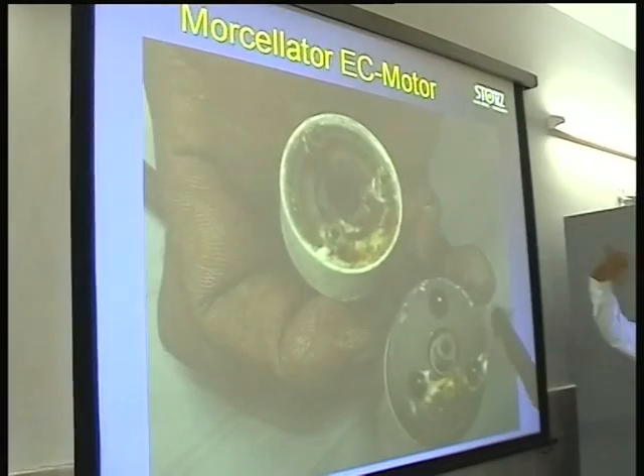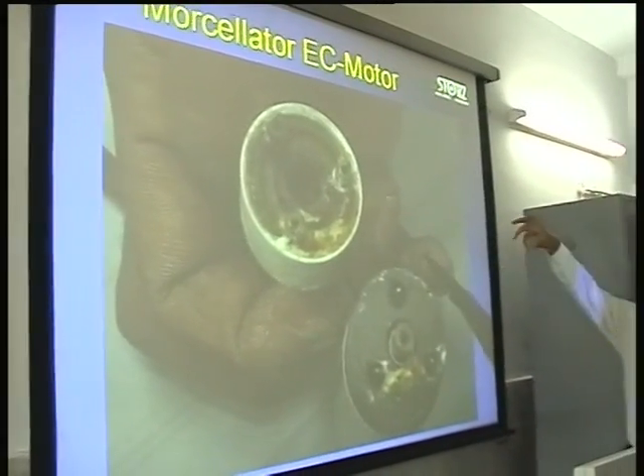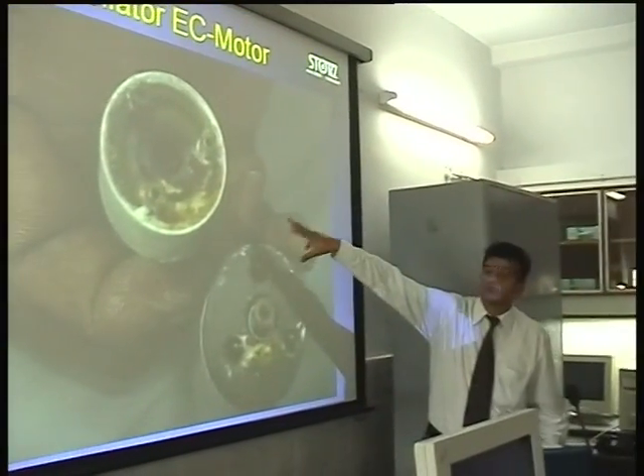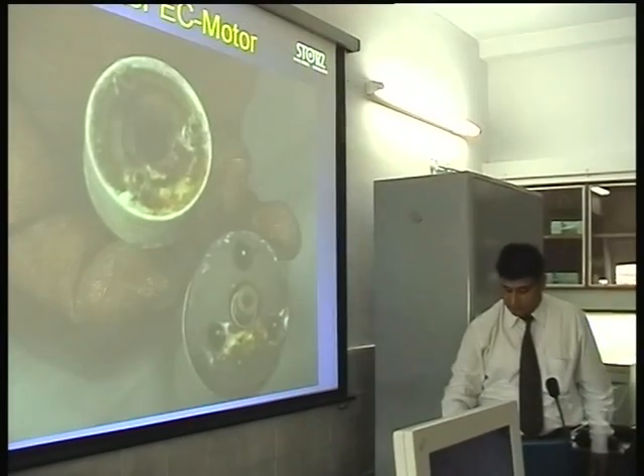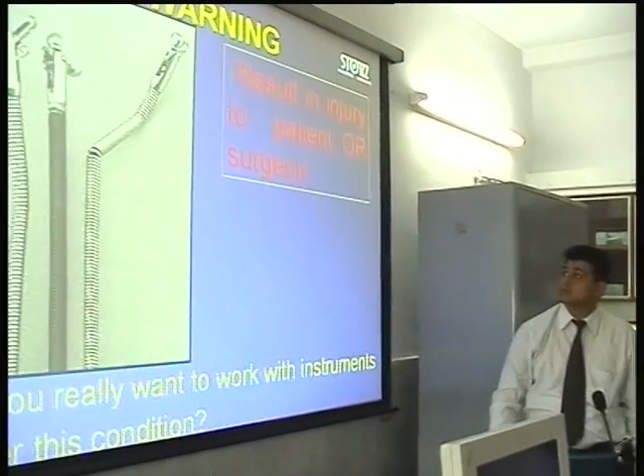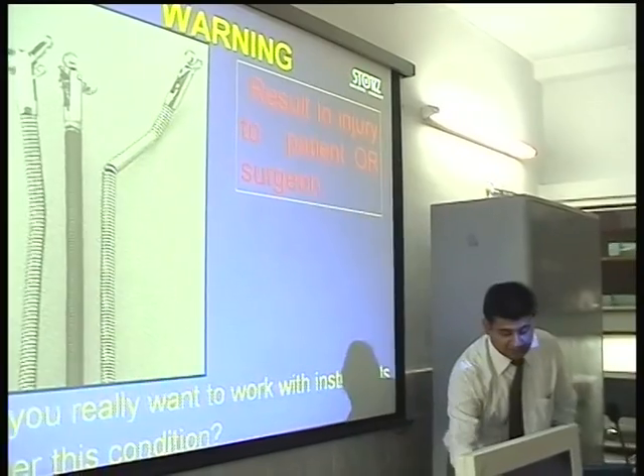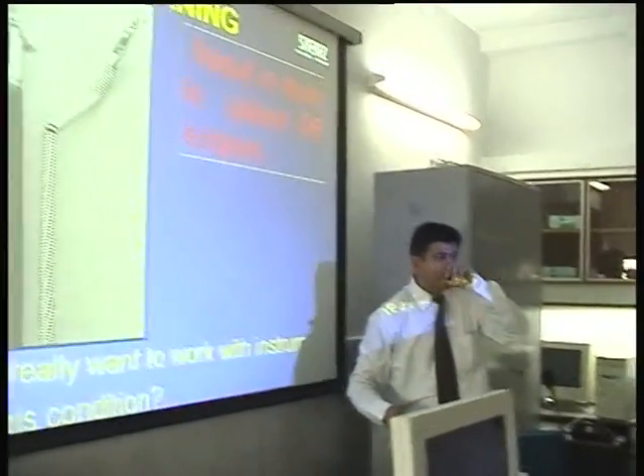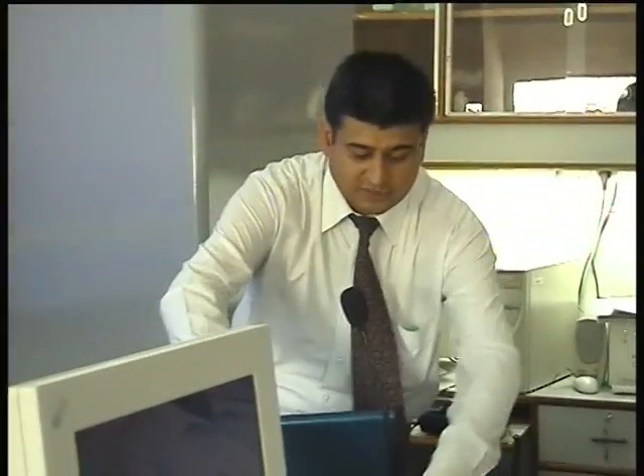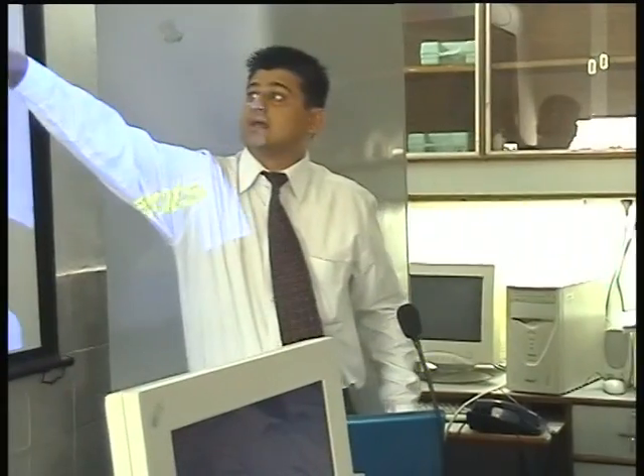Sometimes we are using drills, we are using EC motors. There are areas where we do not open and you find this type of corrosion taking place, hence the equipment gets back. So we have to open and clean it thoroughly. At times, these instruments are long and we forget to get the proper sterilization trays for that. So we have small trays, we try to dump things and they can lead to cracks, and then working with this could be disastrous for the patients.